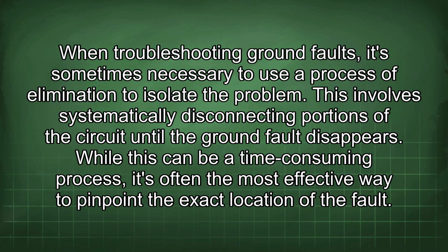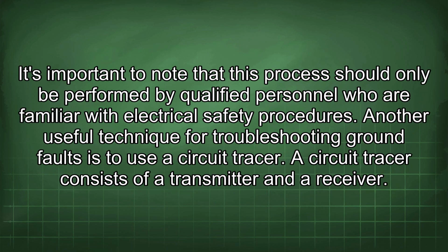When troubleshooting ground faults, it's sometimes necessary to use a process of elimination to isolate the problem. This involves systematically disconnecting portions of the circuit until the ground fault disappears. While this can be a time-consuming process, it's often the most effective way to pinpoint the exact location of the fault. It's important to note that this process should only be performed by qualified personnel who are familiar with electrical safety procedures. Another useful technique for troubleshooting ground faults is to use a circuit tracer.